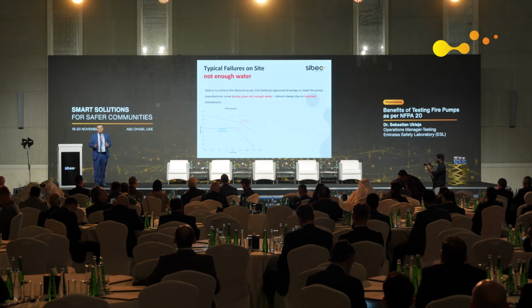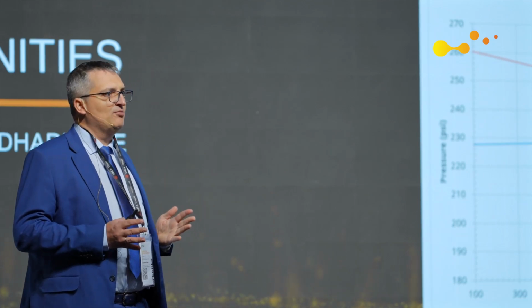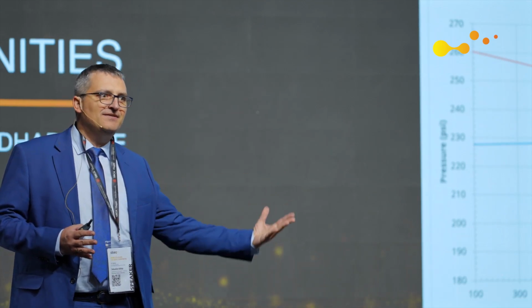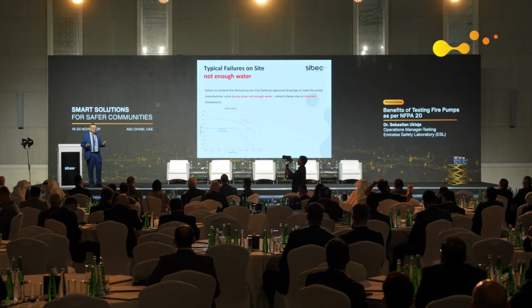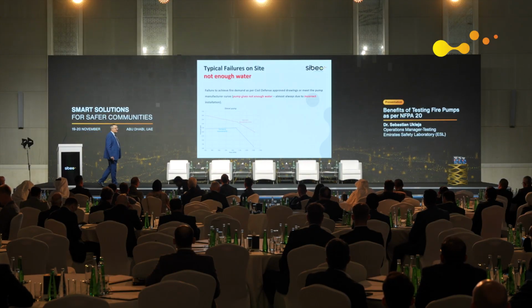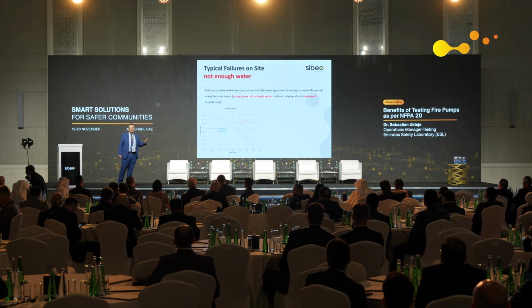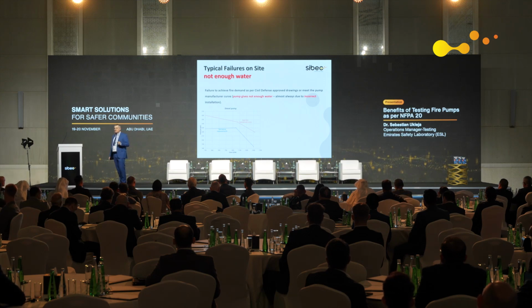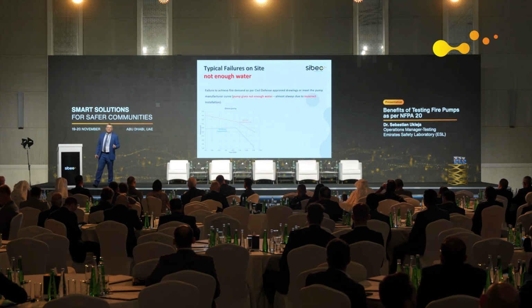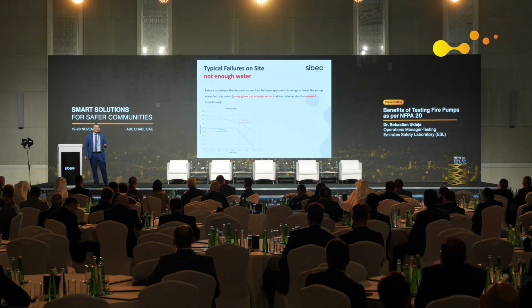So the most common failure we observed is that the pump is not getting enough water. So if the pump is not getting enough water, it cannot deliver the fire demand, or let's put it a different way, the required amount of water for a given building, for a given site. So the problem is: what are the most common reasons why the pump is not getting enough water?